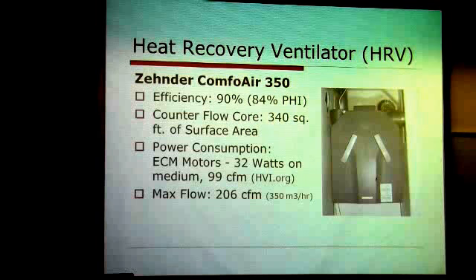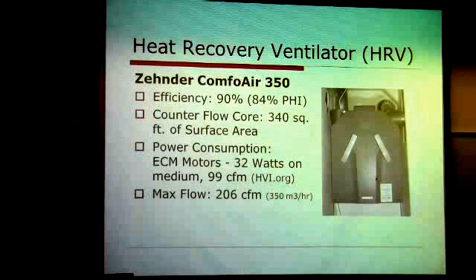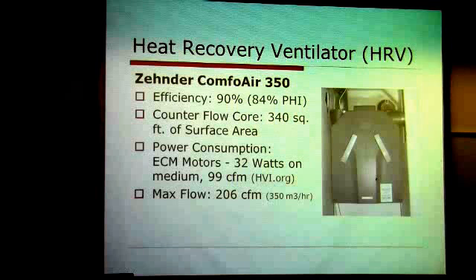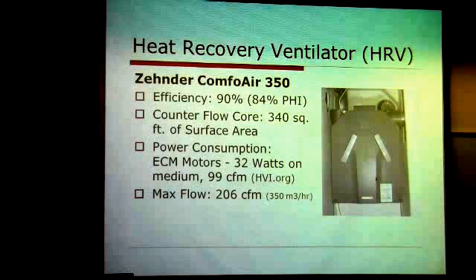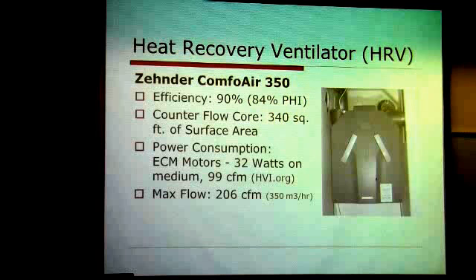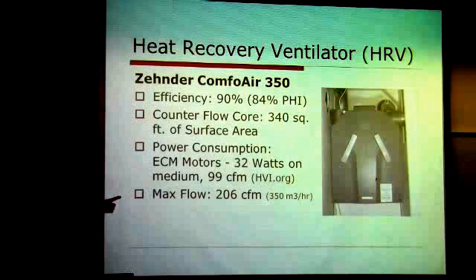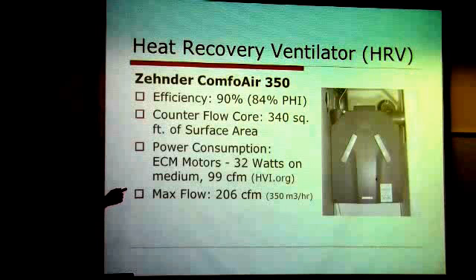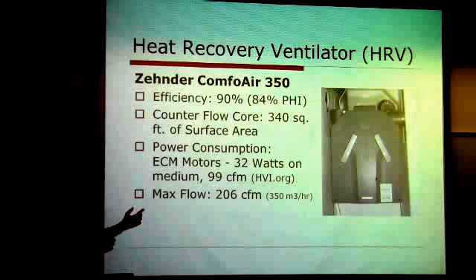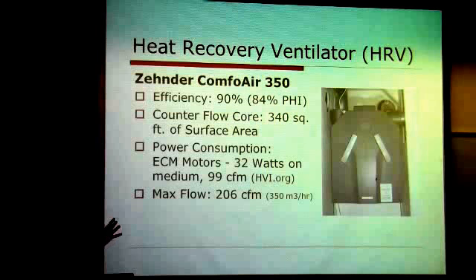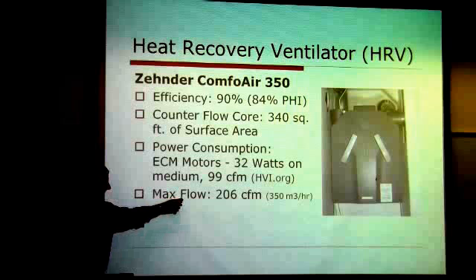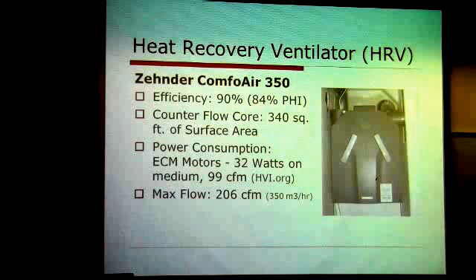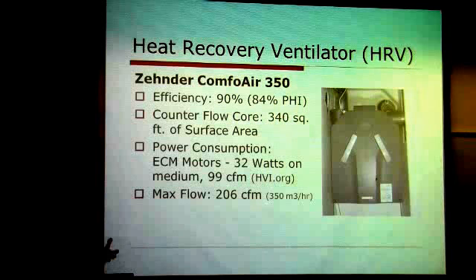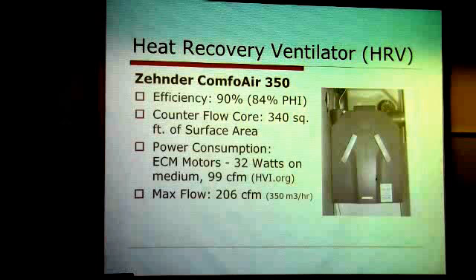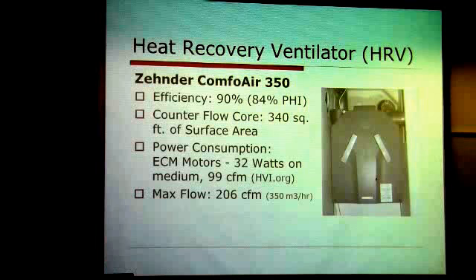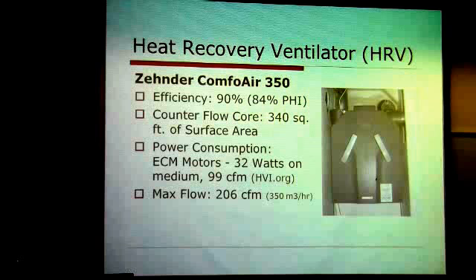Do you know the efficiency for that motor? By chance? No, I just know it's the ECM, and this is the wattage. Anyway, the best efficiencies occur when you're running continuous speed at about 50%. Somewhere 40 to 60% of maximum speed gives the best electrical efficiency, and then you still have a boost button. So when you're in the bathroom or cooking quite a bit in the kitchen, you can boost the system up to level 3, which would be 30 to 40% higher.